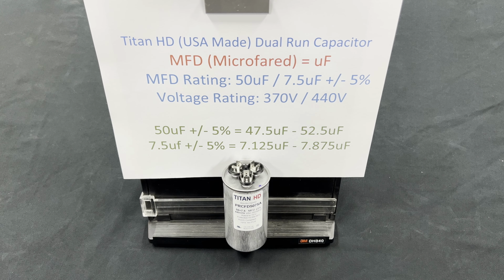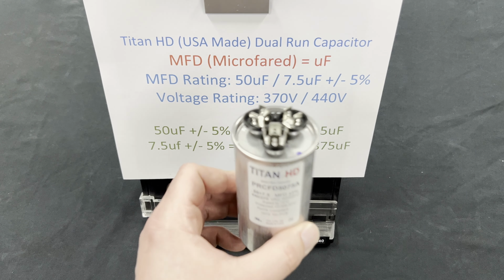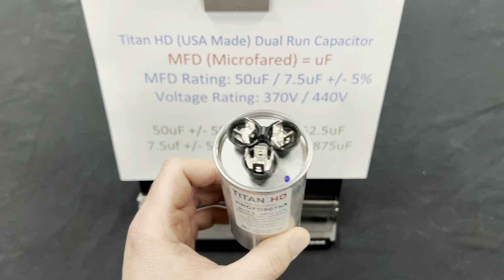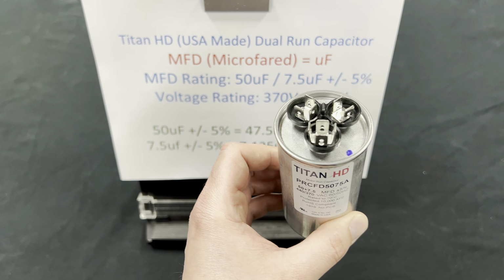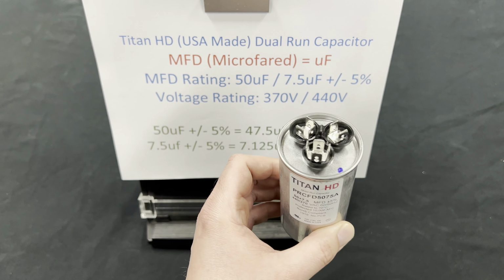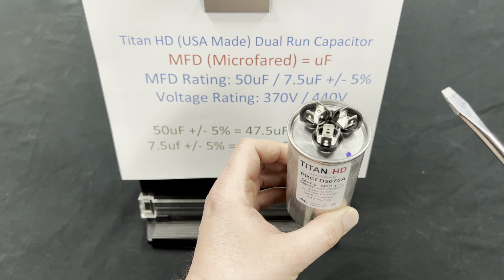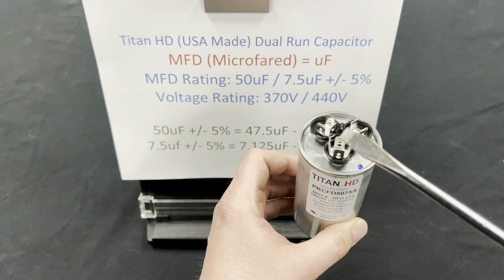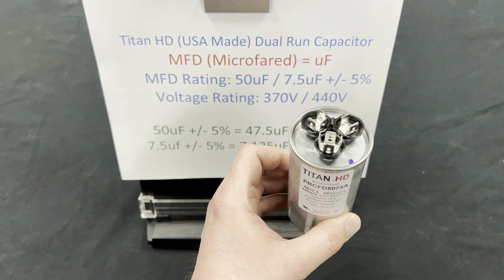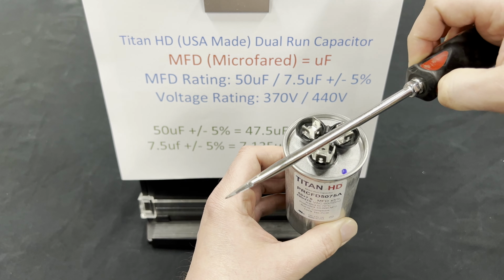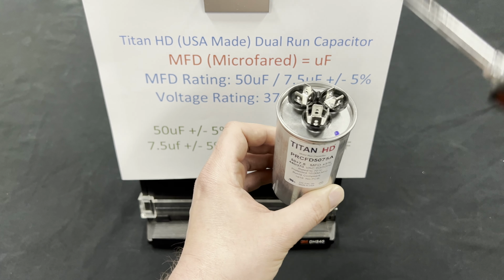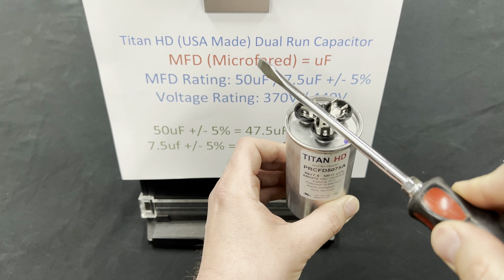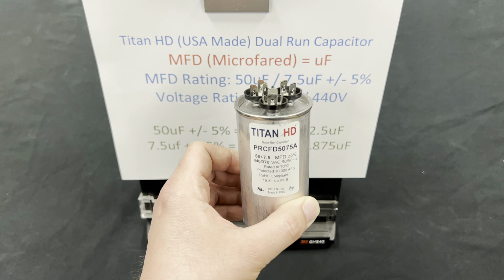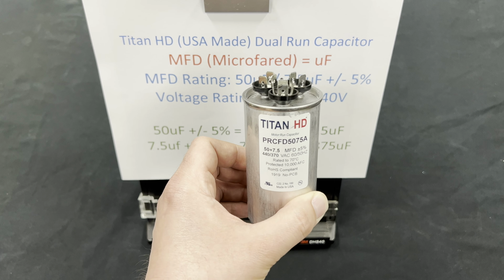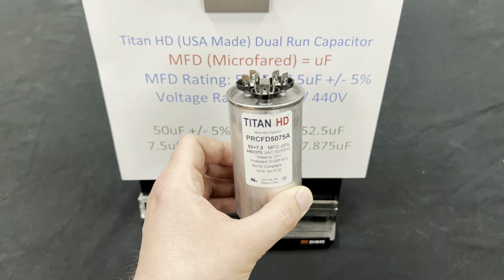A safety tip before working with any capacitor is to make sure that it's discharged. The way you would do that is take your capacitor, find the common terminal, and what we're going to do is take an insulated handled screwdriver and short it between the common and the fan, and then the common and the Herm, to make sure that there's no built-up charge left inside of it. In this case, we had no charge. If you did, you'd get a little bit of a pop and a spark, and that would make sure that your capacitor is discharged.